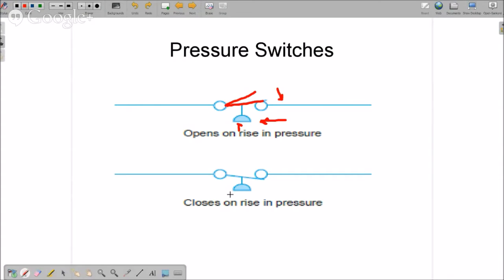Same thing on this one. This is close on rise in pressure. So if the pressure is pushing up on that little cup, at the design closing pressure this switch will be closed. As the pressure falls, it eases up that pressure on that little cup and it will open up that switch.